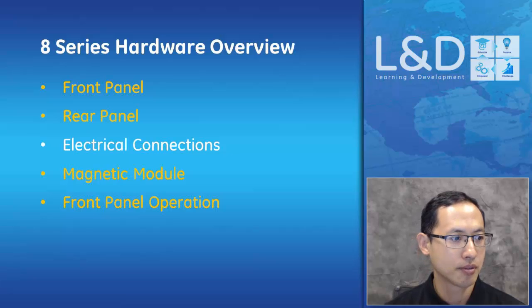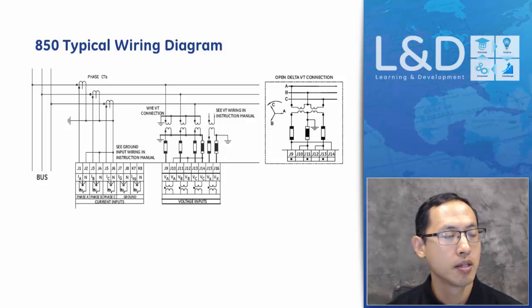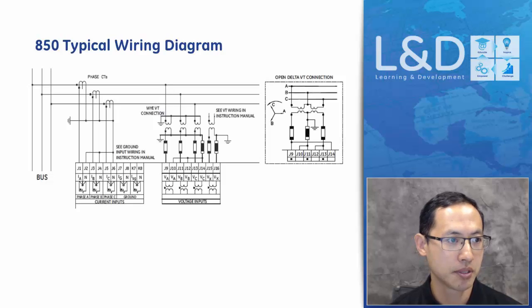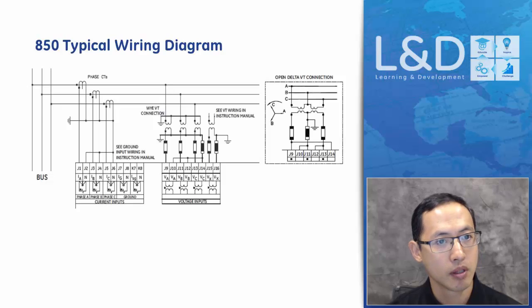Electrical connections. So this is the typical 850 feeder relay wiring diagram, and we can see the current uses the J card for the input. For the VTs, it has two types of wiring, the Y connection and the open delta connection. For the open delta, we need just 2 VTs.